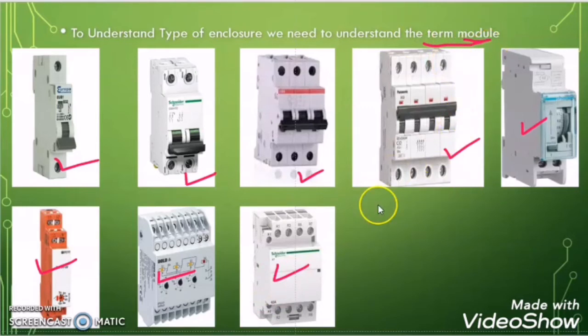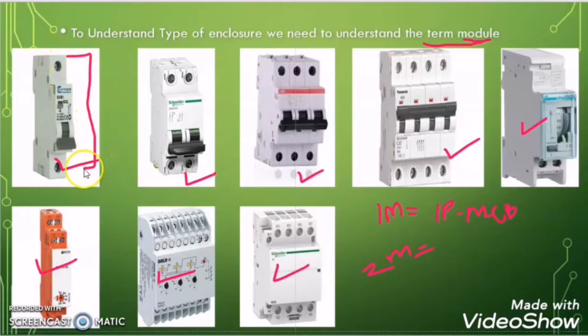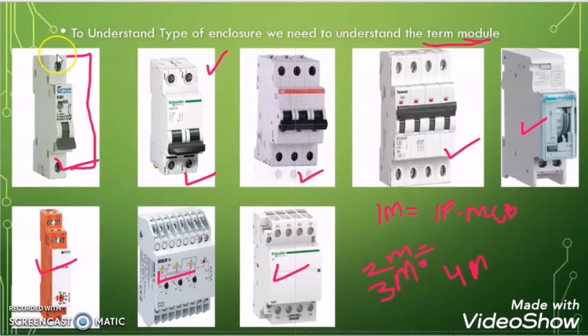We have to understand what the module represents. One module represents that there is a space to install one single pole MCB. Two modules represent space for two single pole MCBs or one double pole MCB. Three modules represent space for three single pole MCBs or one three pole MCB. Four modules represent space for four single pole MCBs or one four pole MCB.